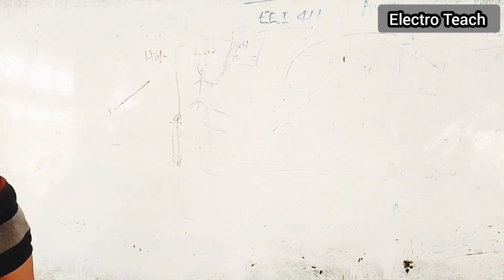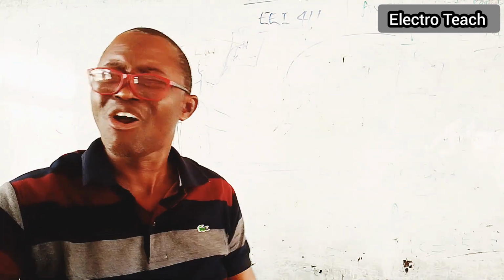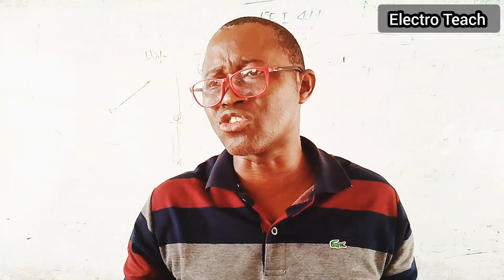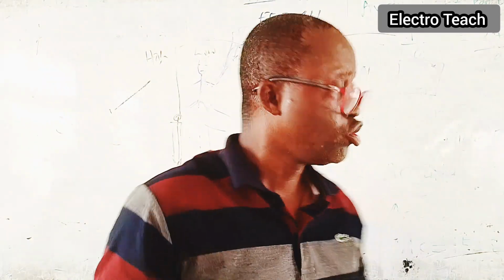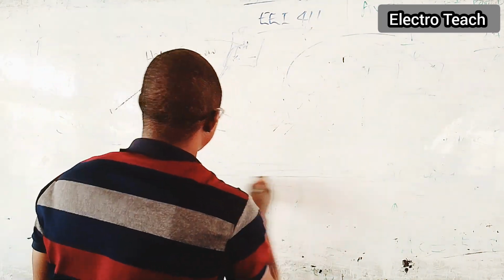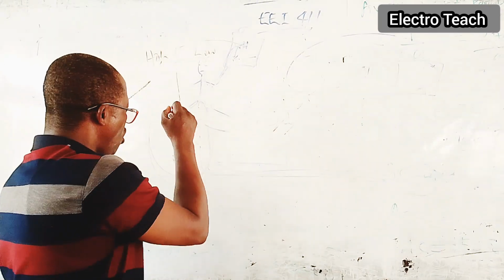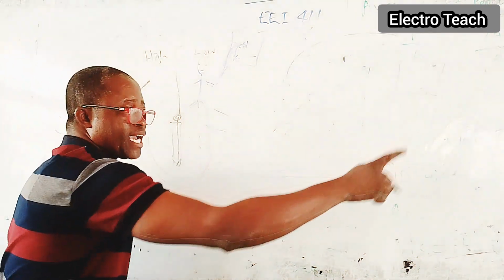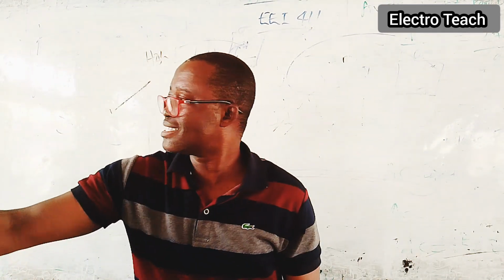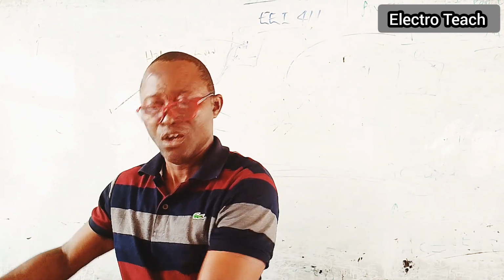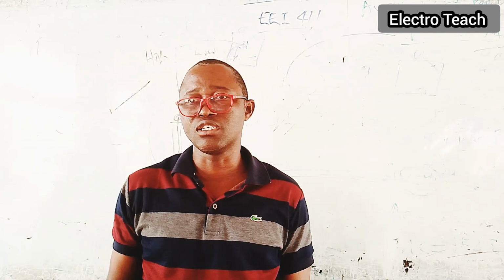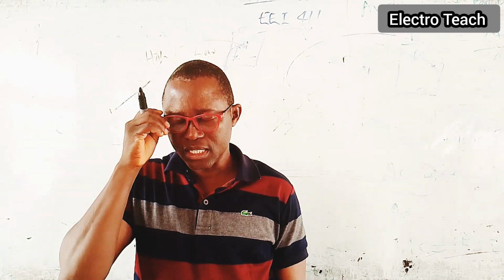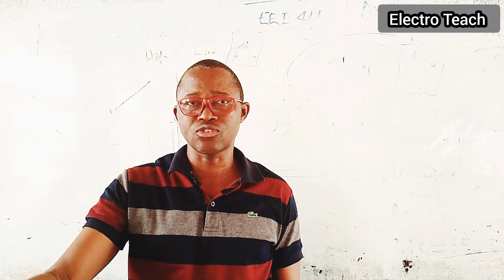That is why we want to tell you about these steps. Under normal standard installation, when you finish the installation, you must carry out earth resistance tests around the building on the electrode, to check the behavior, the resistance of the soil where that building is located. That is the first thing we are treating.